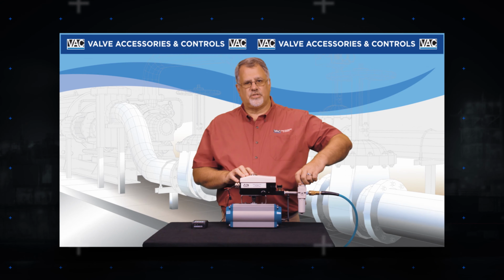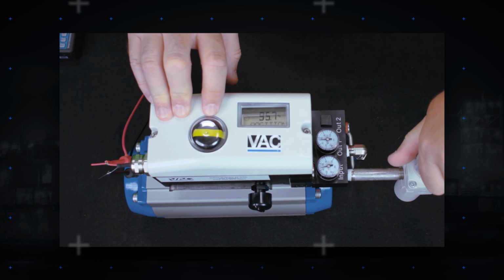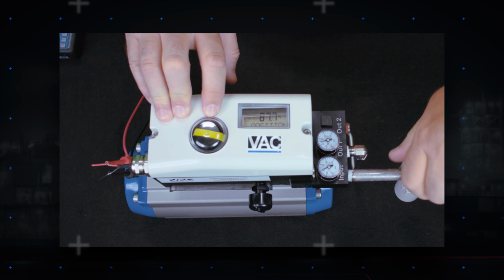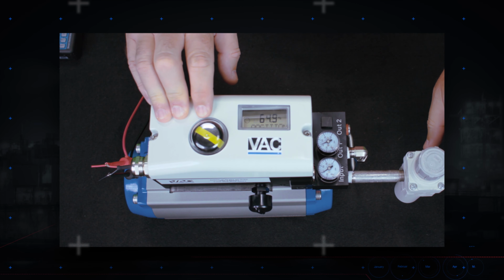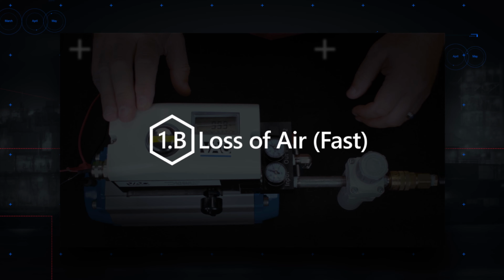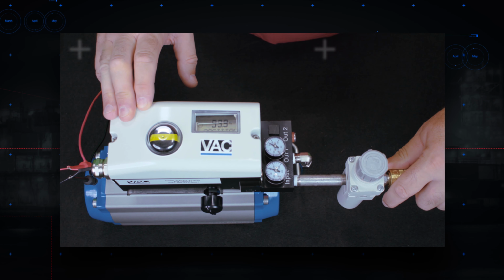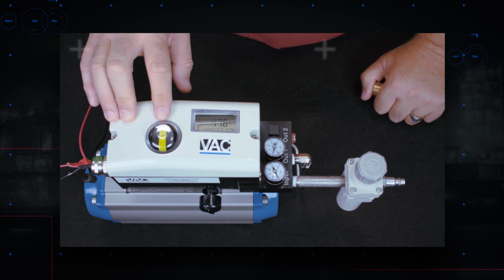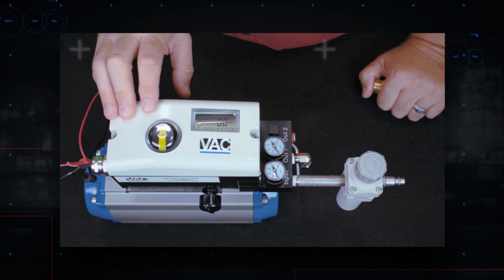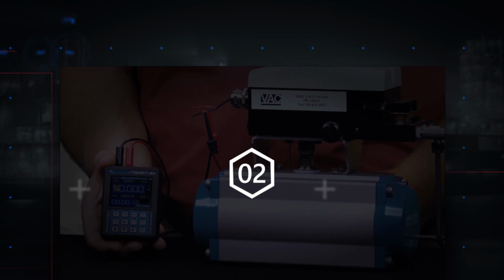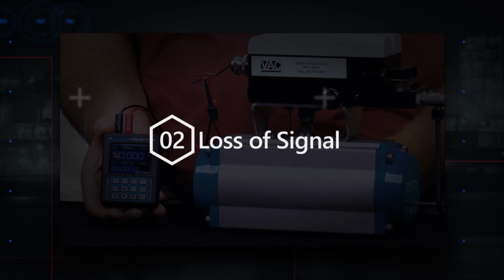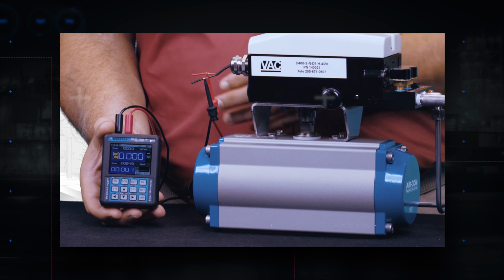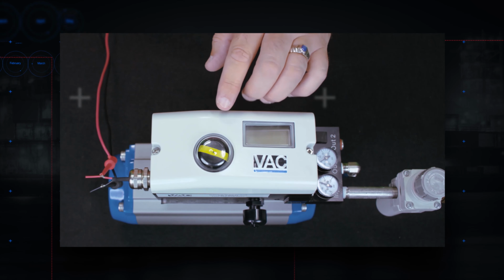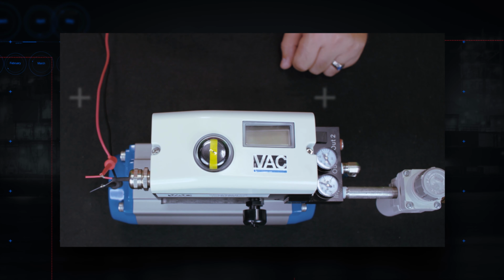When the air pressure drops slowly like this, note that the valve will move slowly towards the closed direction. When the air pressure is removed suddenly like this, the valve will move to the closed position. When I remove the electrical signal like this, the valve will move to the closed position.